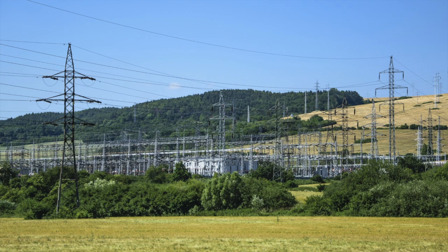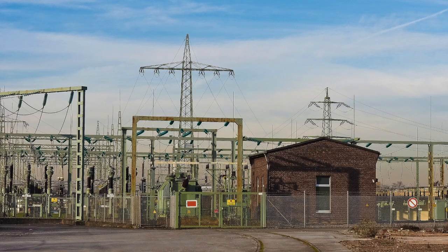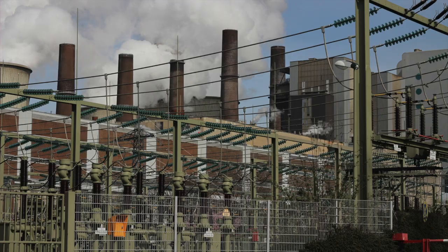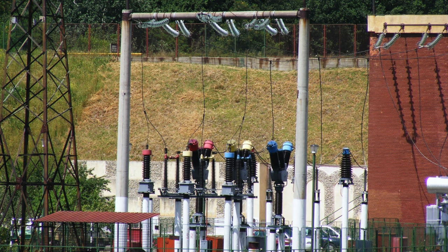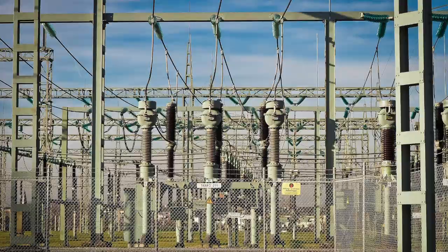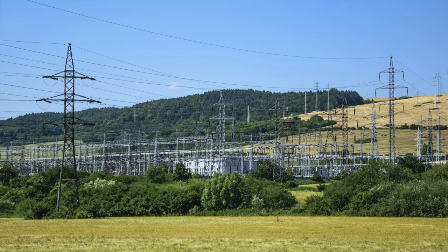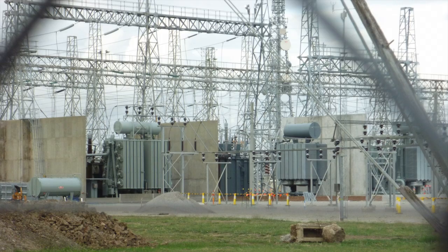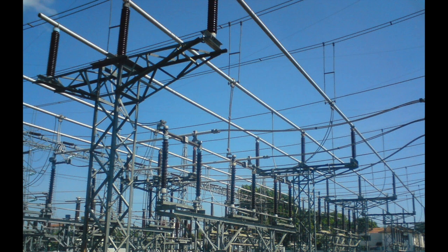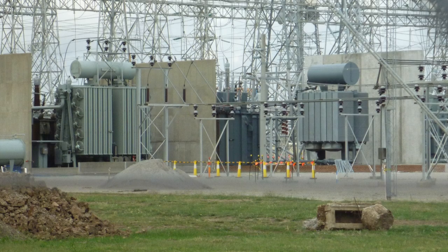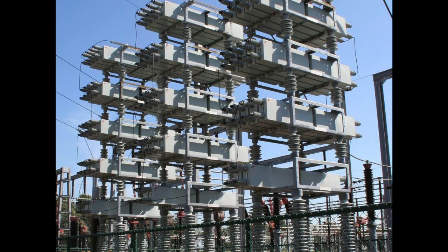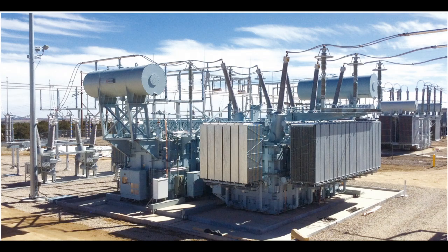Substations are where transmission lines connect to transmission lines, or where transmission lines are converted to distribution voltages. There are different types of substations. For this video, we'll cover transmission and distribution substations. Transmission substations connect 2 or more transmission lines. Transmission substations contain devices such as high voltage switches to allow for switching or isolating lines, transformers to convert between voltages, protection and control equipment, and correction devices and phase shifting transformers to control power flow.